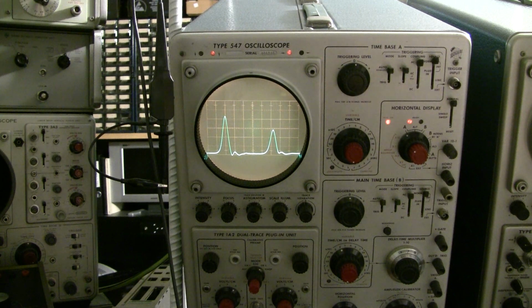I've done no alignment on this scope, and I don't know of any alignment that's ever been done to it. As I say, when I got it, all I did was blow the dust out of it and lubricate the fan, and it's been running ever since. Not even a single tube I've changed inside this. So all those myths about these things being hard on tubes and that kind of stuff are just myths. I have lots of these old scopes. I have another 547 here and a 565 over there, and none of them have any problems. I haven't replaced a tube in any of them. So maybe I'm just lucky. Sure is a handsome oscilloscope.